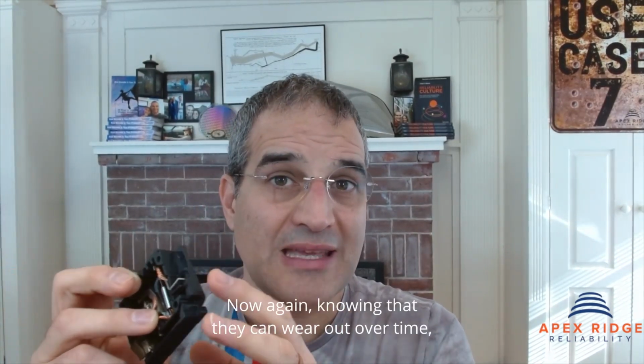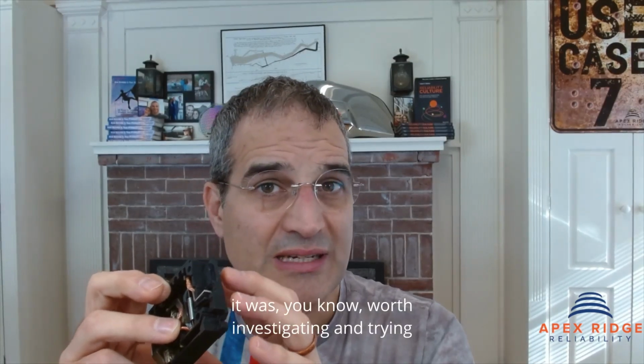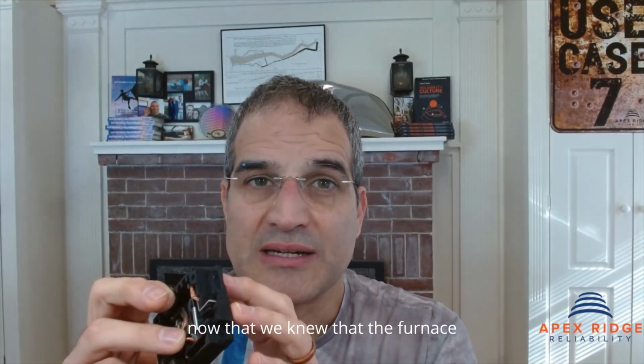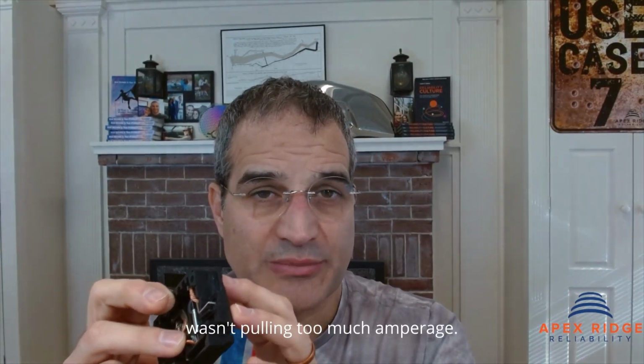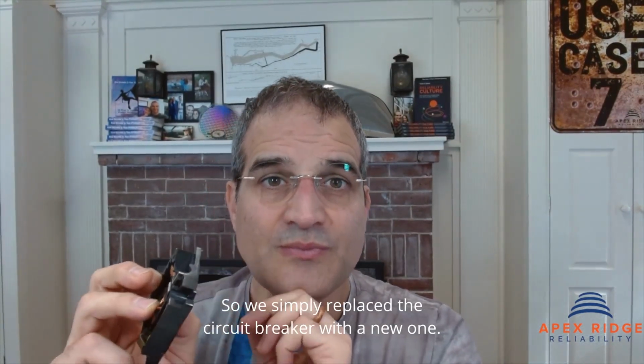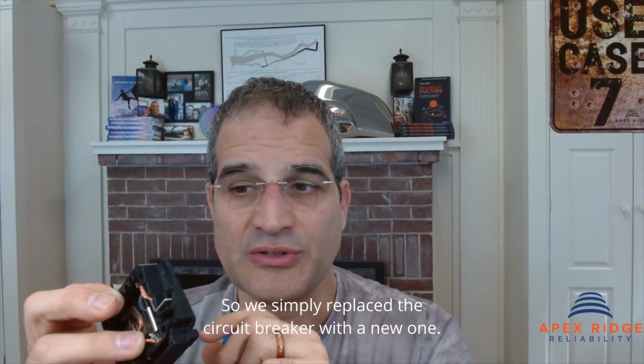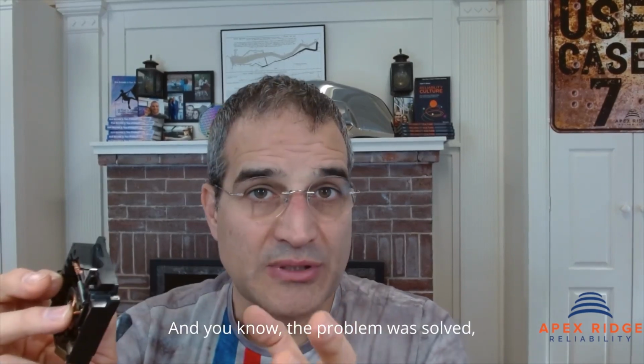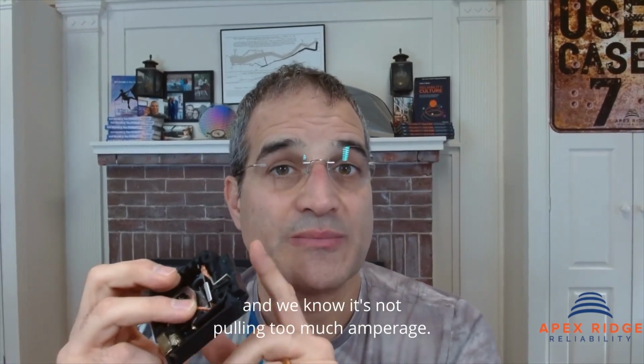Now, knowing that they can wear out over time, it was worth investigating, now that we knew the furnace wasn't pulling too much amperage. So we simply replaced the circuit breaker with a new one, and the problem was solved. We know it's not pulling too much amperage - it was the circuit breaker.